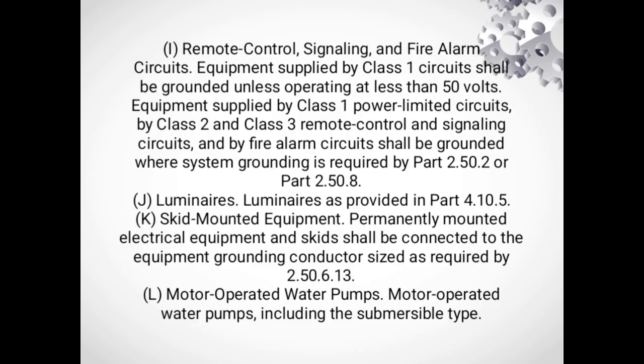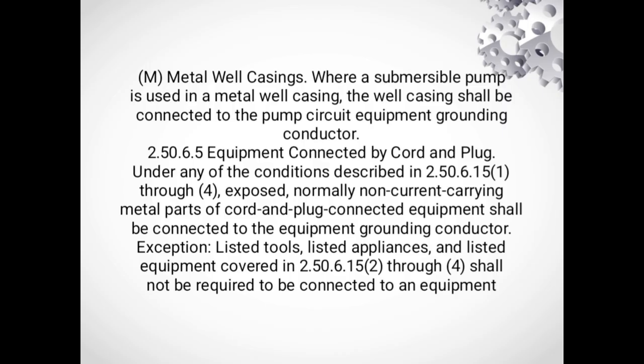Equipment supplied by Class 1 power limited circuit, by Class 2 and Class 3 remote control and signaling circuit, and by fire alarm circuit shall be grounded where system grounding is required by Part 2.50.2 or Part 2.50.8. J. Luminaires as provided in Part 4.10.5. K. Skid mounted equipment: permanently mounted electrical equipment and skids shall be connected to the equipment grounding conductor sized as required by 2.50.6.13. L. Motor operated water pumps, including the submersible type. Metal well casing: where a submersible pump is used in a metal well casing, the well casing shall be connected to the pump circuit equipment grounding conductor.